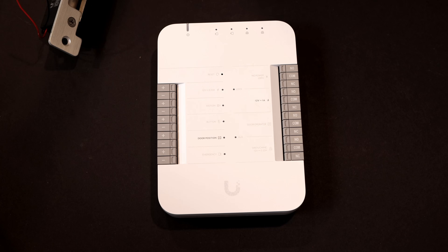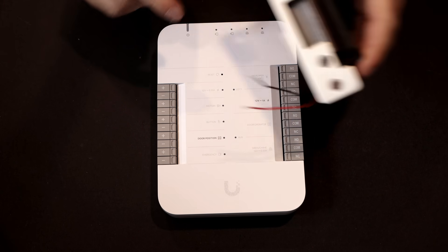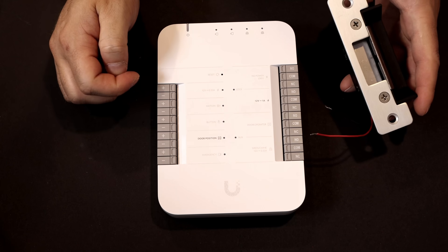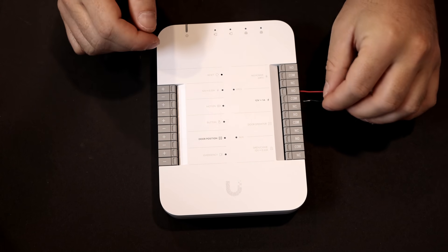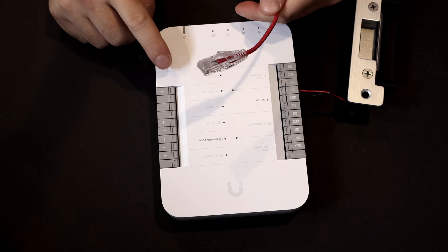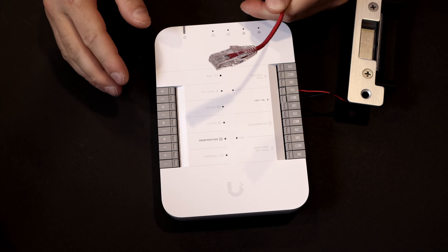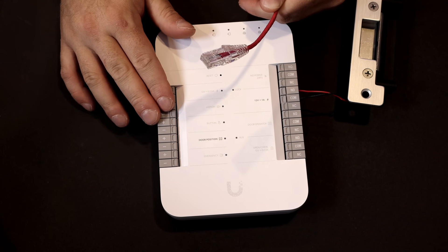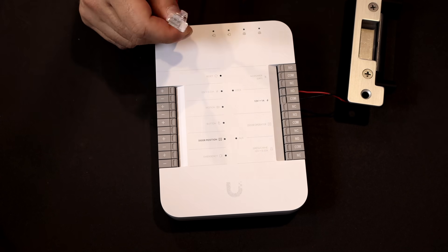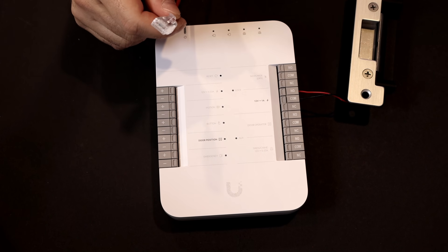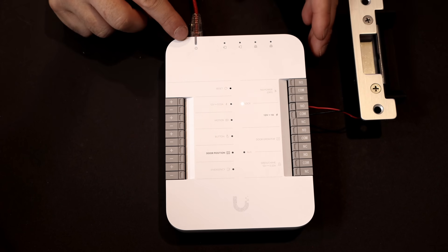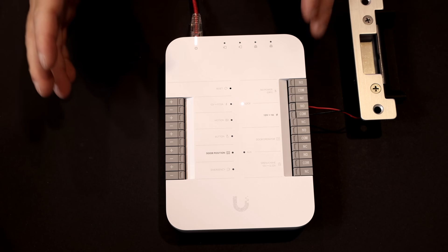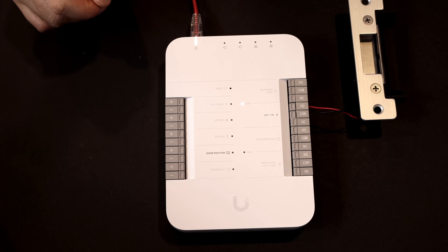Now, the next thing that we need to do, we need to get this all hooked up. I do have a UniFi Access electric strike, so I'm going to put that into the 12 volt 1 amp. Our red wire is going to go to the normally open, and then our black wire is going to go into the com. Now, we need to connect an ethernet cable to give this power, and we need to power the hubs up with PoE++, so that we make sure that our readers, and all the accessories that we're putting on here, get enough power, and they don't start shutting down. I'm going to connect this ethernet cable to the power port, and this is connected to my mission critical switch, which has PoE++. You should be able to see this light going on and off, and it is a white light, as it's not currently adopted into our controller, but we will get to that shortly.